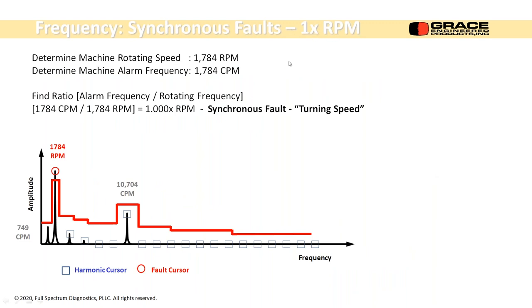Synchronous faults are at 1 times RPM. The label on the pump or on the motor, the nameplate data, is probably going to tell us roughly what the unloaded speed of the motor is when it came out of the shop that built it. Okay. Yours is going to be a little bit different because you're hooked up to another machine, so there'll be some load on it, so it might slow it down a little bit.